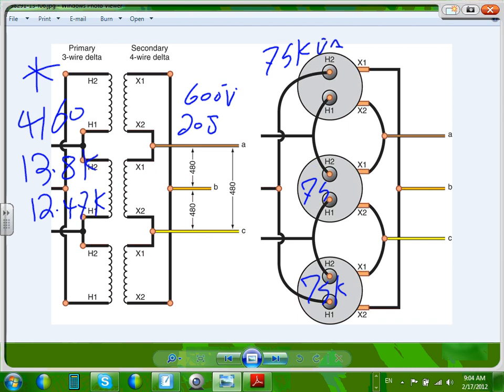So the advantage of this system, I don't like to emphasize it because we don't have control over it for the most part. The advantage is if one of these transformers is to crap on you, burn, you can hook it open delta, but that's utility work though. You hook it as open delta, you can rehook this one and your system is still up and running at a derated value. So that's an advantage. So you rehook it, go bring another transformer, put it back, and you're up and running.